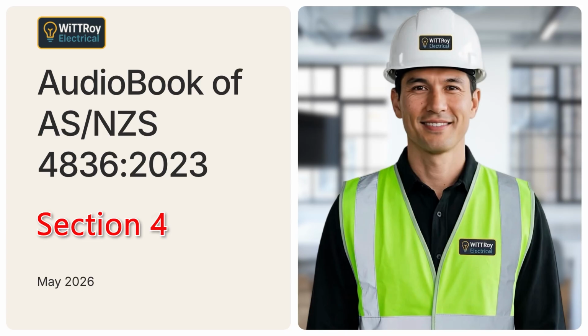Clause 4.3.15. Control measures when leaving work unfinished. Clause 4.3.15 explains how to leave a work site safe when the job is not finished. The work site must be left safe for access by other people. Exposed conductors should be terminated in a way that provides suitable protection, including IP2X protection. They should also have mechanical protection or restraint.